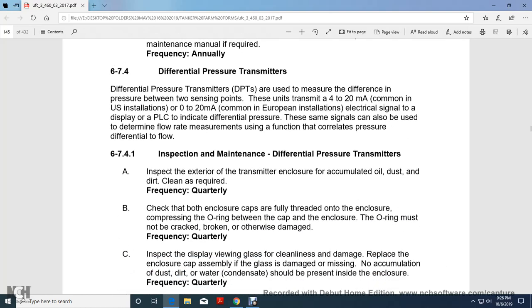Now for the differential pressure transmitter. A differential pressure transmitter measures the difference between two sensing points, with a 4 to 20 milliamp electrical signal displayed on the PLC to indicate the differential pressure. The same signal can be used to determine the flow rate, as a function correlating the pressure differential to flow.